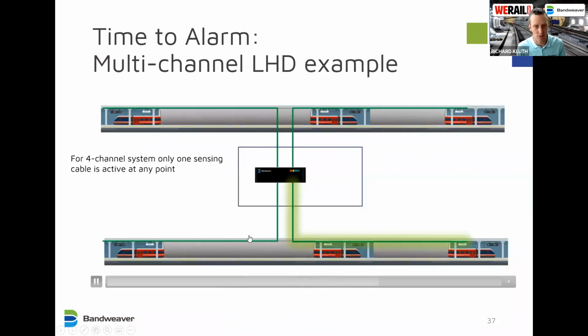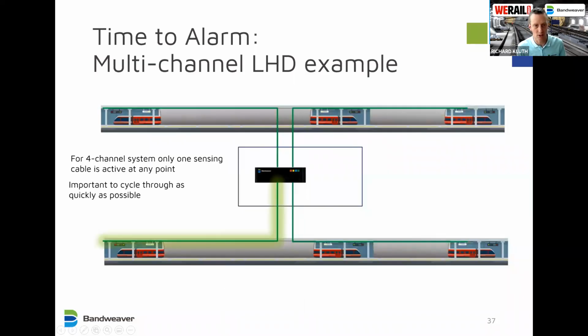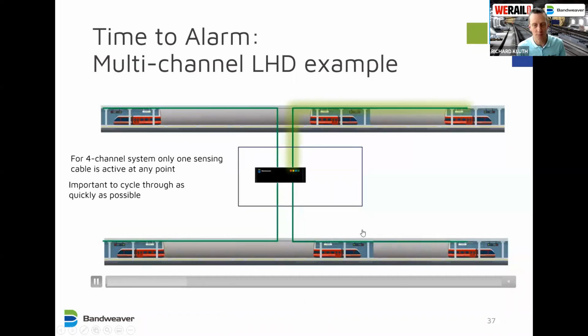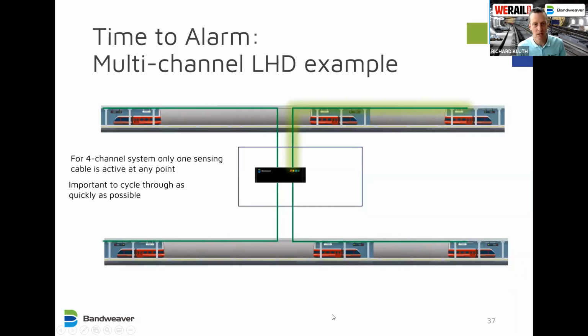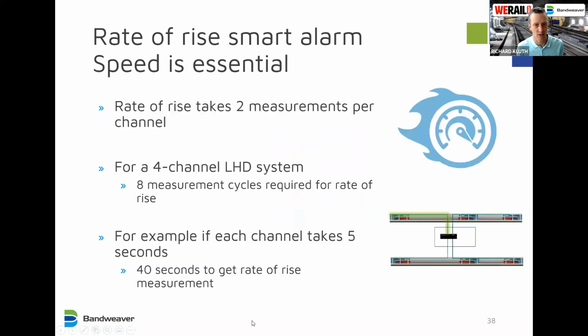So you want to make sure you cycle through as quickly as possible, so you're not having big gaps in any coverage. But then also, it's important, we talked about the rate of rise. With the rate of rise, you have to have 2 cycles to get through. You have to see the change in temperature. So that again changes the dynamics of how fast the measurement is.